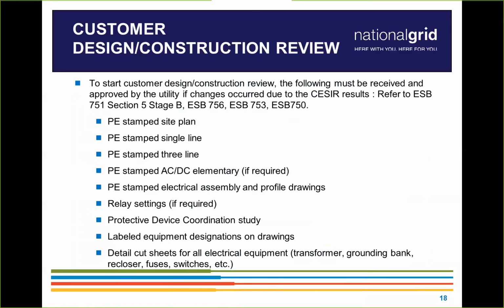Then we'll move on to the customer design and construction review. Now, to start that, we're going to need a full package of drawings and submittals: the PE stamp site plan, the PE stamp single line, 3 lines, PE stamped AC/DC elementary, the PE stamped electrical assembly and profile drawings, any relay settings if they're required, protective device coordination studies, labeled equipment designations in all the drawings, and then any cut sheets that are associated with your project, such as transformer, grounding banks, reclosers, fuses, and switches. And Chris will get into that in a little bit more detail as we go on.